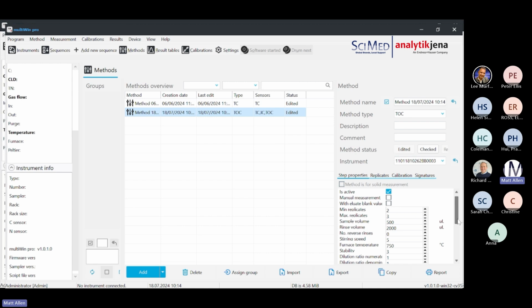But below is where we actually fine-tune the method. So, for example, the amount of replicates. So we're running 2 from 3. We could run 2 from 5 or 5 from 5, for example. We've got a sample volume of 500. So with this instrument, it's 100 microliters all the way up to 1 ml that we could change the sample volume to. And we've got the default rinse volume of 2 ml. And we've also got a stirring speed set for the stirrer bars within the vials, and the default furnace temperature of 750 degrees.